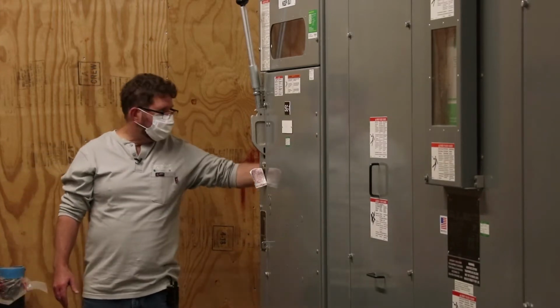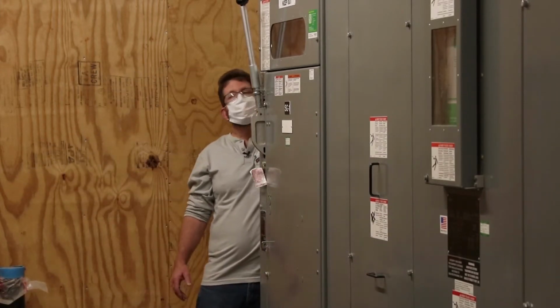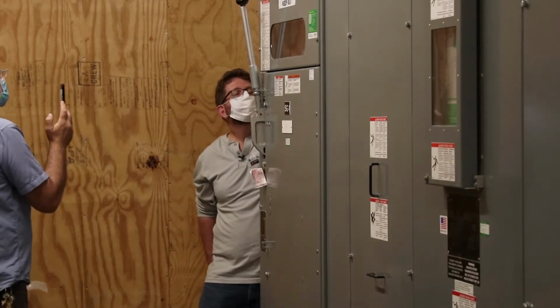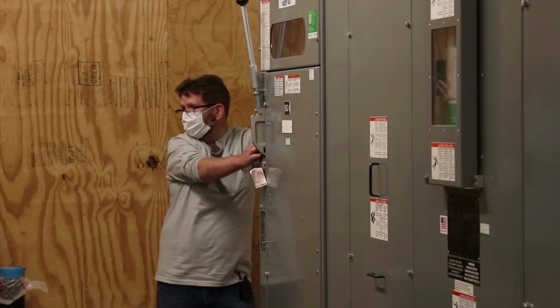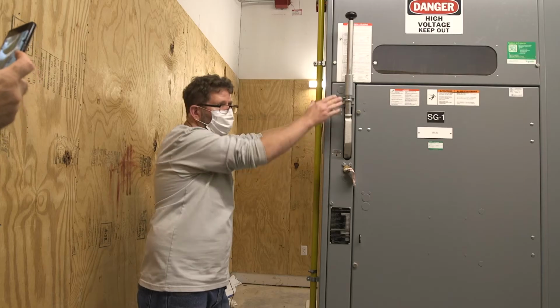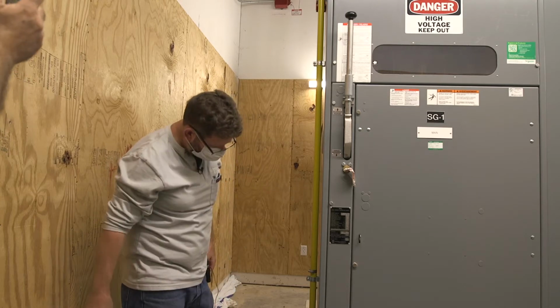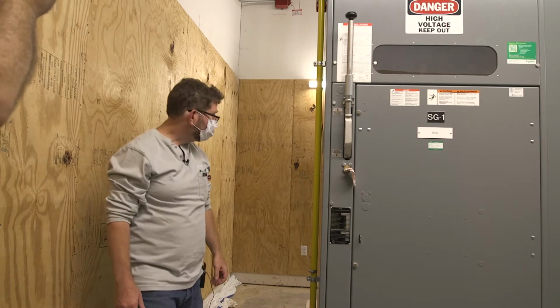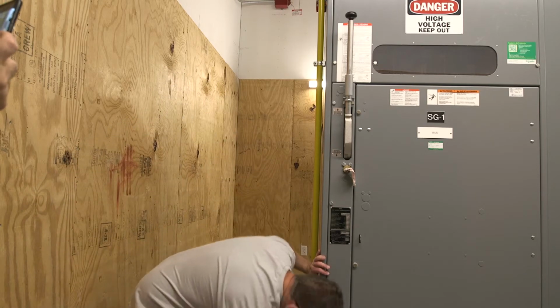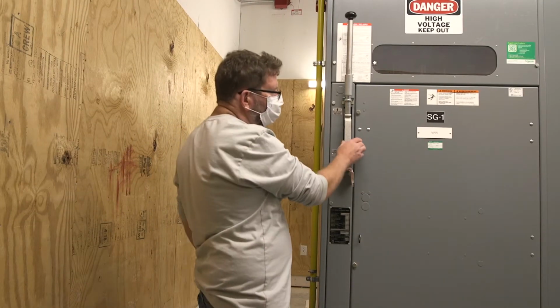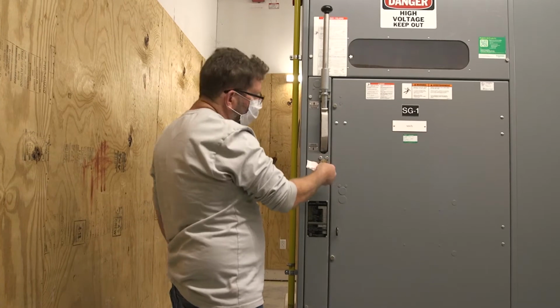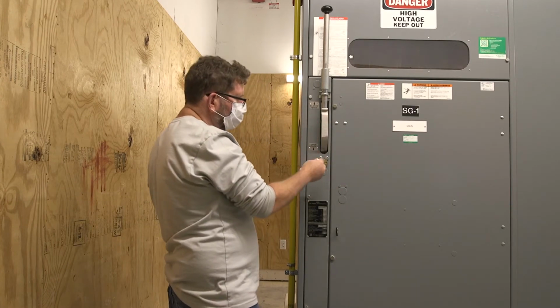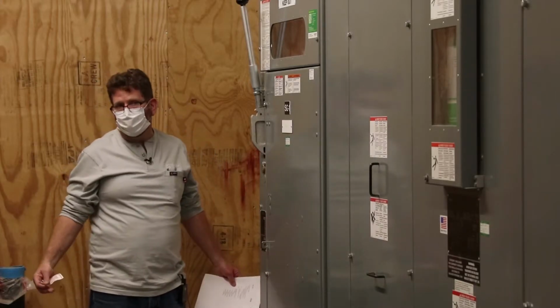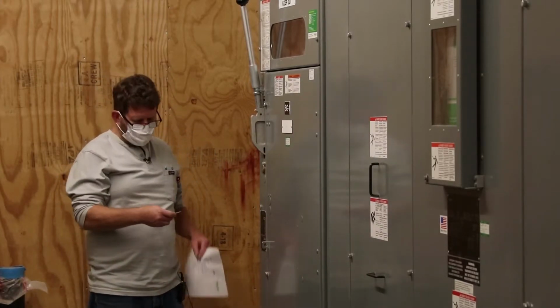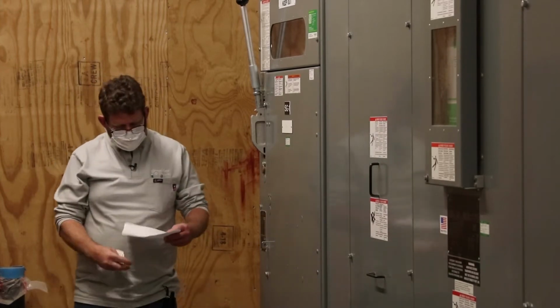You do have a maintenance accessory on the side of the gear. It's a fuse puller. Obviously, you would never pull these fuses out live. You'd have the switch open, locked, and you have a hot stick to pull the fuses out. This key interlock will prevent you from opening the switch without the key, but it also prevents you from closing the switch without the key. You never want to open or close the switch with the main breaker in and closed, just to minimize load on the switch when you operate it.